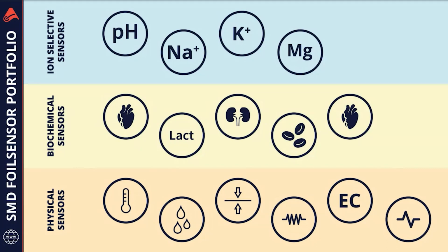On top there are the ion selective sensors like pH, sodium, potassium, magnesium. We've been doing this for 5 or 6 years, so we have deep know-how here and create calibration-free sensors. This means we have the ability to bring the sensors to a level where you don't need a one-point calibration — you can just take it and use it.